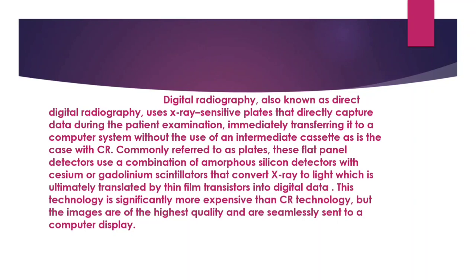This is ultimately translated by thin film transistors into digital data. This technology is significantly more expensive than CR technology, but the images are of high quality and seamlessly sent to a computer display. In CR, an imaging plate is used, while in digital radiography flat panel detectors are used. The scintillation material converts X-ray into light, which is an analog signal, then converted into a digital signal by using an analog-to-digital converter.